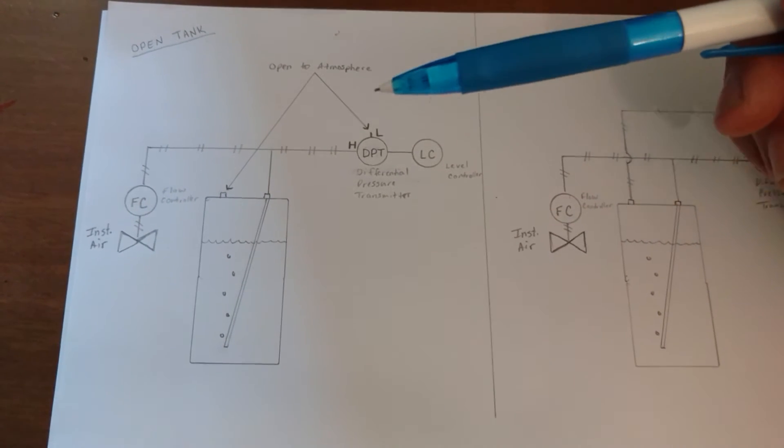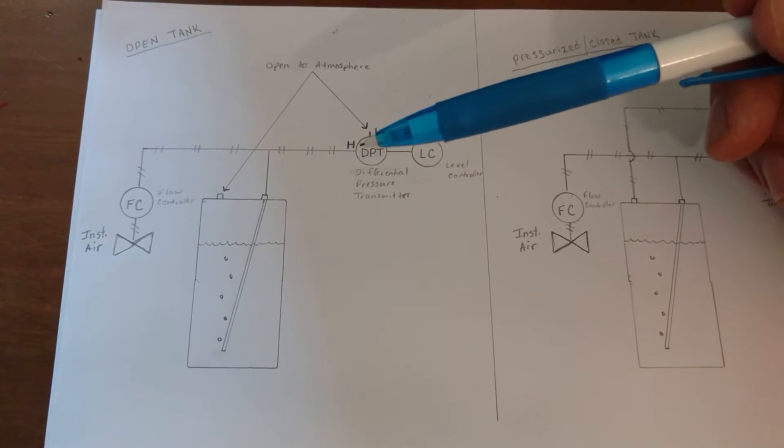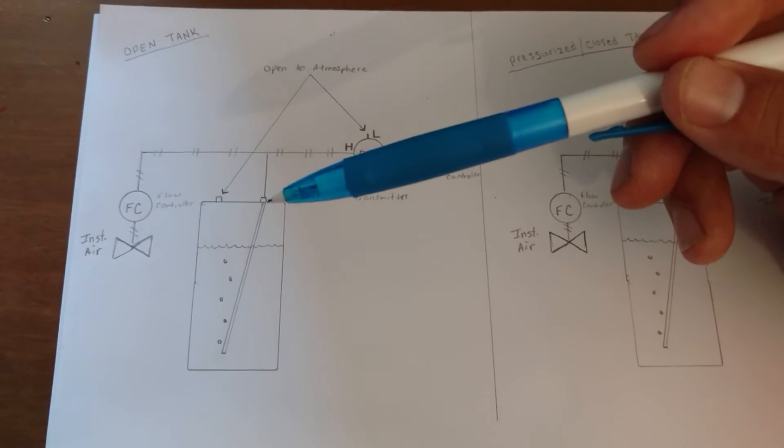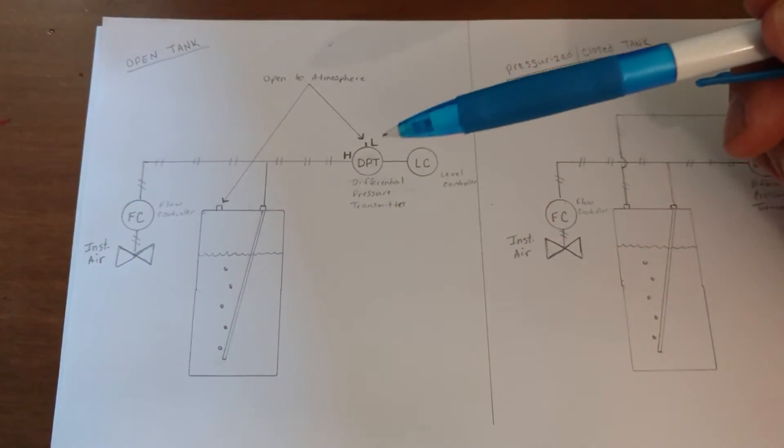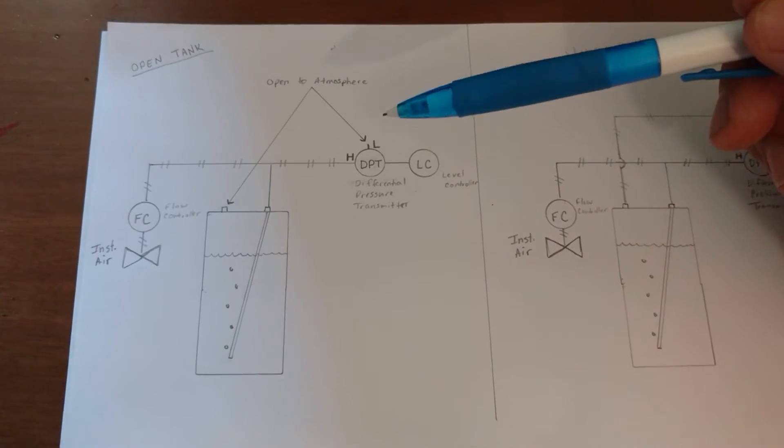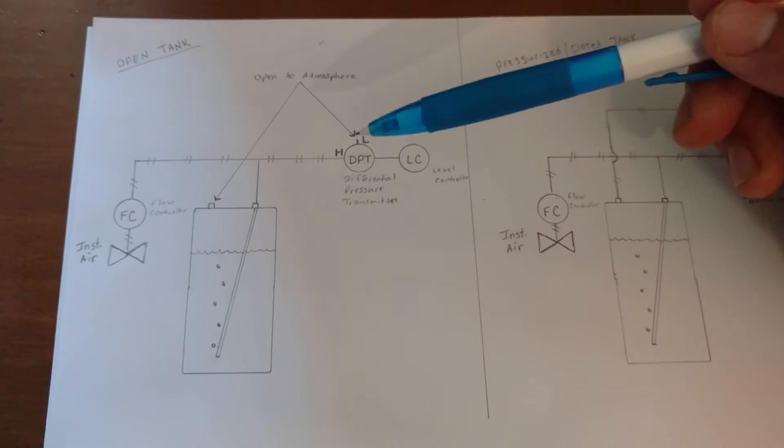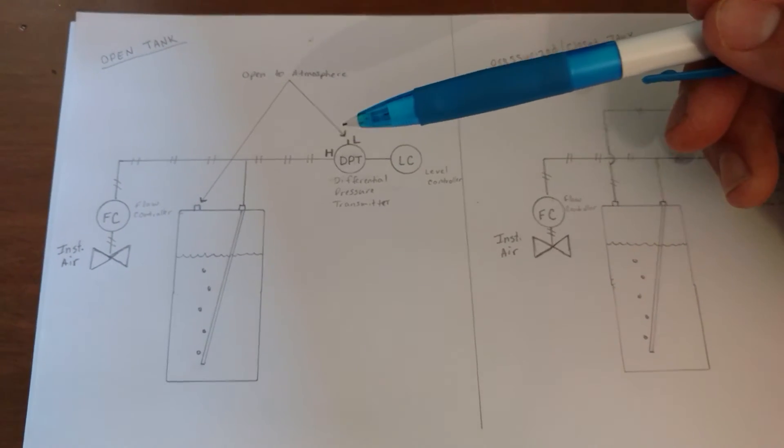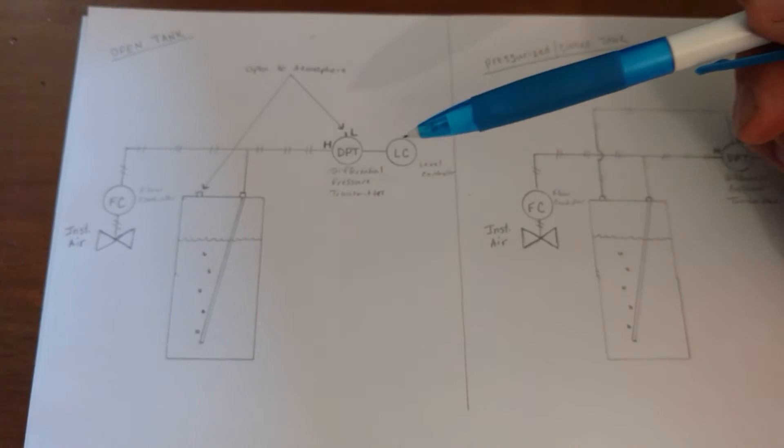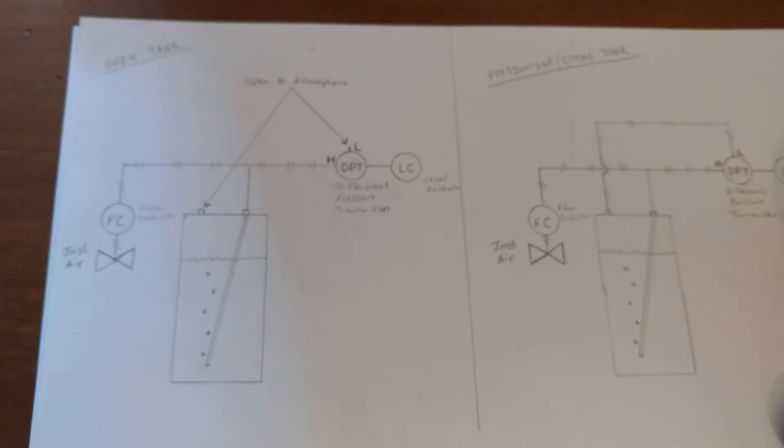So what's happening here is the high side is connected to our pipe, and the low side is not connected to anything. It's also vented to atmosphere, and it does its job by comparing the high and the low and sends an electric signal to our level controller, and we can find the depth.